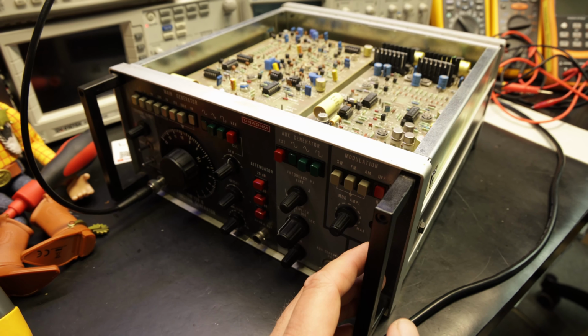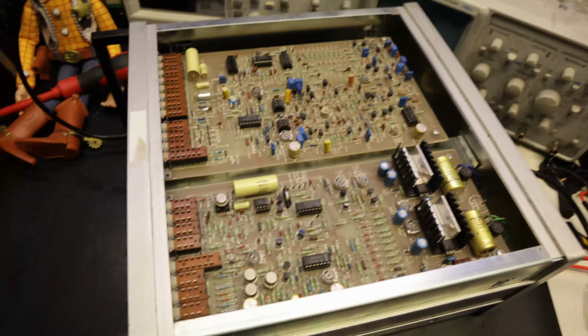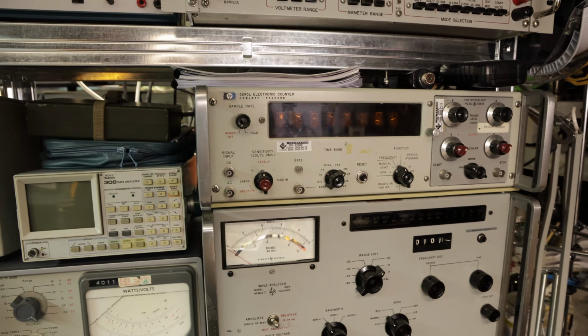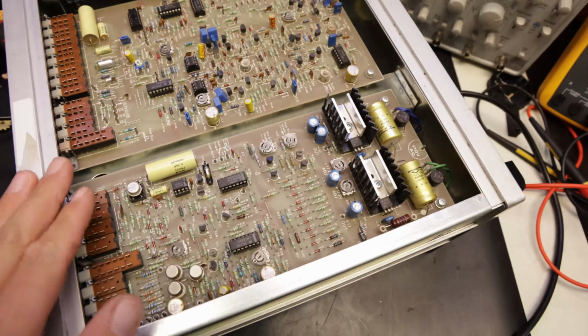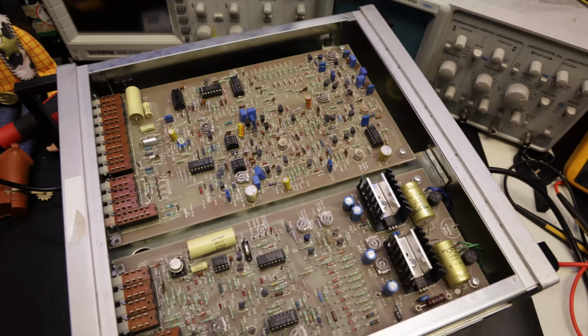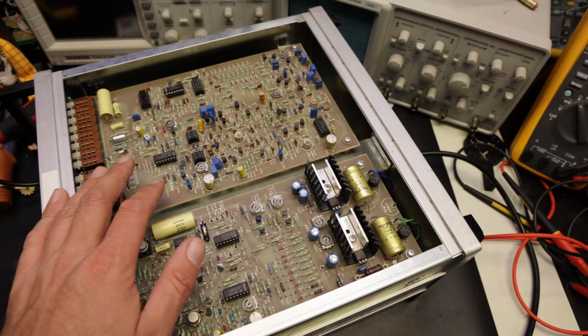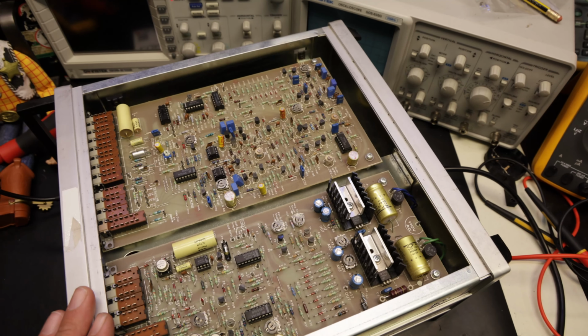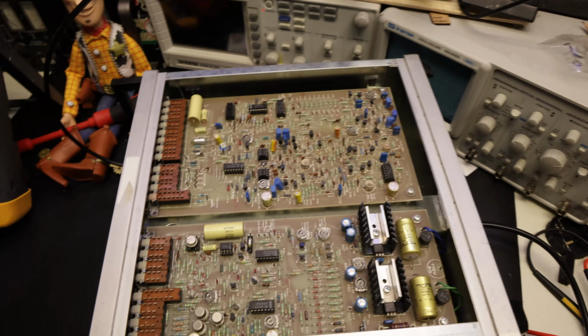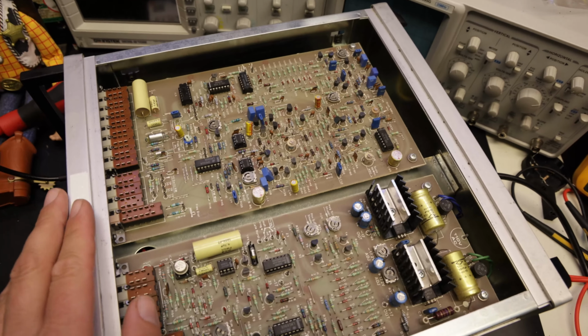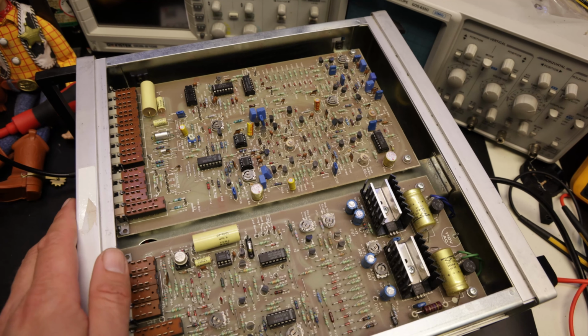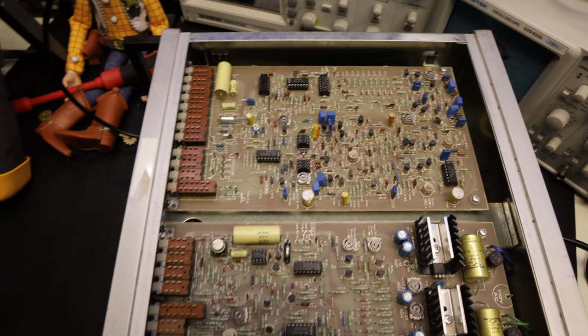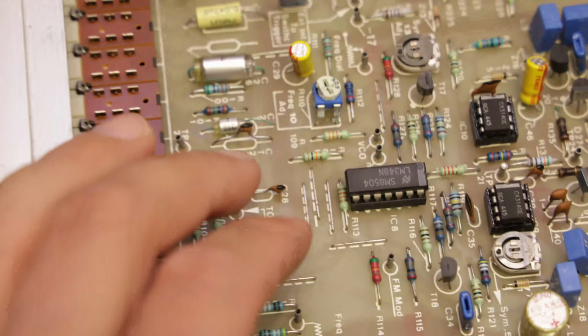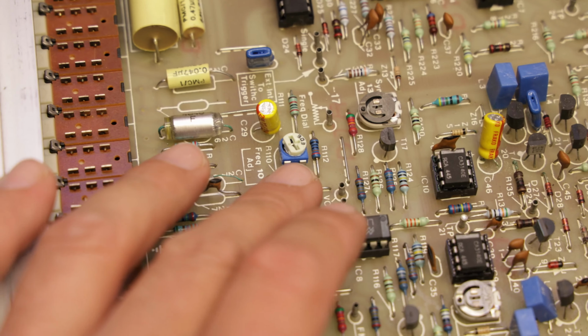So, on my way when I was calibrating, I used my old HP counter, and I was a bit back and forth connecting and disconnecting, and suddenly it stopped working and I couldn't figure out what was happening. Everything was in spec and calibrated, and it just stopped working. No signal out, I got power out but no waveform, and it turned out to be the calibration pot set here, which had broken into 2 pieces suddenly.